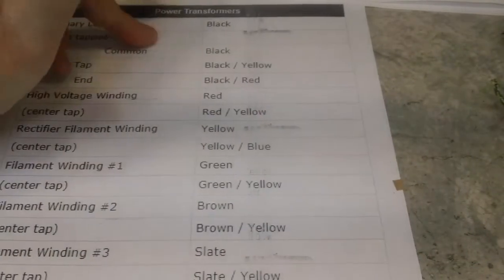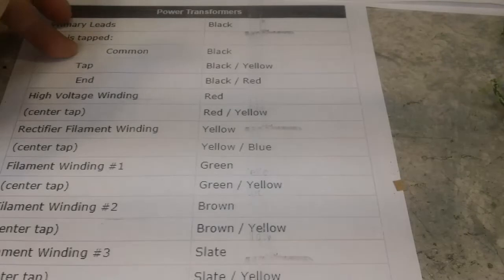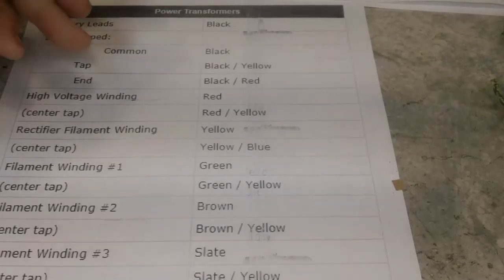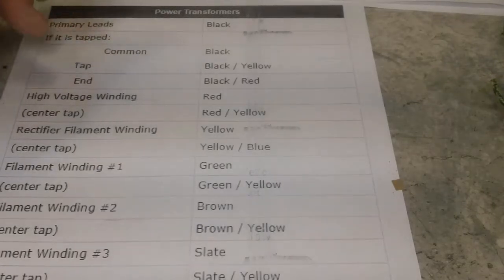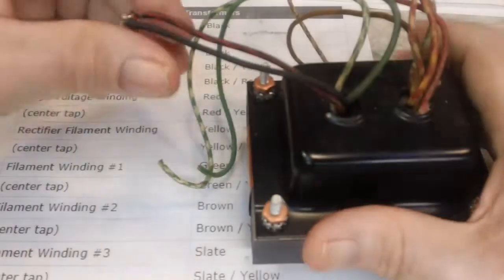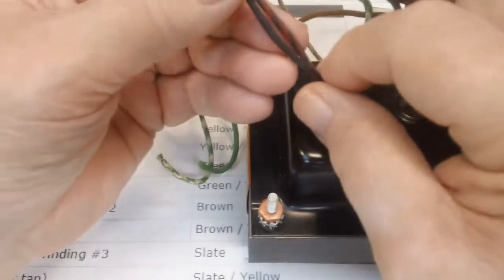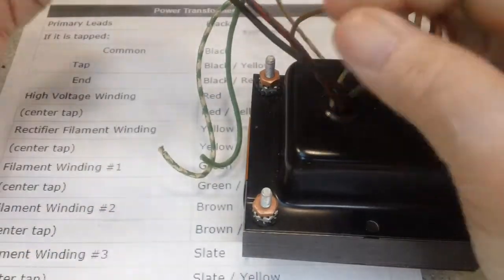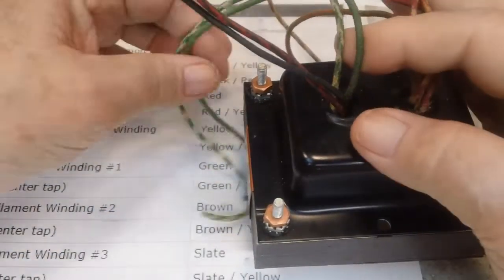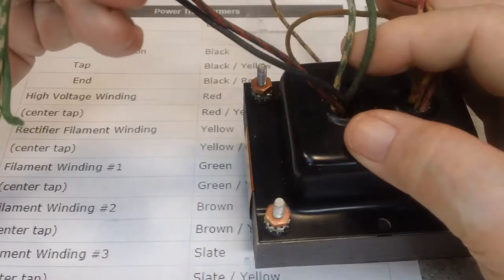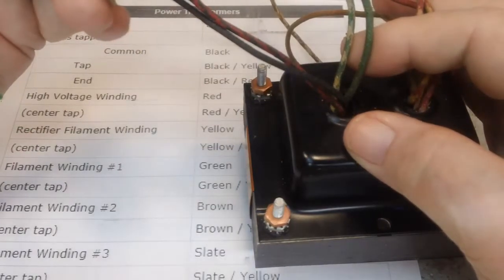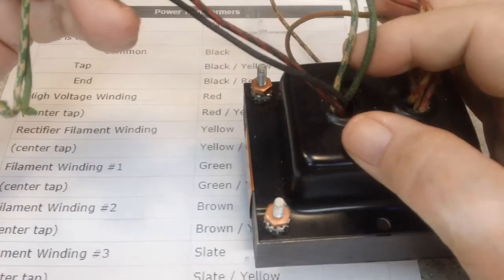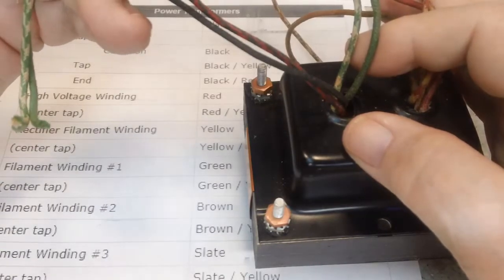According to this, primary leads are black, and if it's tapped, the common is black and the end is black-red. Now I've got that coming out of here, so I've got a black and a black-red right there. Also coming out of the same hole I have two more leads, which I'm assuming are the taps off of that primary - one is green, one is green-yellow.